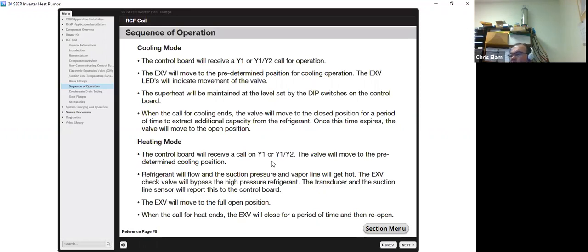In heating mode, the control board will receive a Y1 and/or a Y1, Y2 signal. It will move to the predetermined cooling position. The refrigerant will flow. The suction pressure will rise and vapor line will get hot. The EXV check valve will bypass the high pressure refrigerant. The transducer and the suction line sensor will report this to the control board. At that point, the EXV will move to the fully open position. When the call for heat ends, the EXV will close after a period of time.